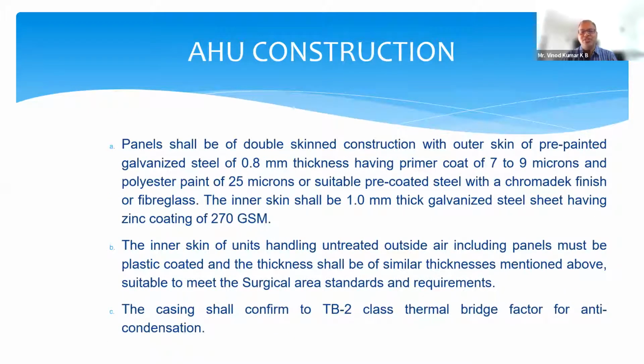Now look at the double-skin AHU construction. The outer skin has to be of 0.8 mm thickness, and the inner skin has to be of 1 mm thickness. That is the construction that we talk about, which is how sturdy the AHU is going to be. These are the guidelines as issued by AHU. So I'm giving you the standards which you can actually copy into your tender specifications, or your consultants whom you have employed can be made to use these standards in their selections. And the inner skin has to have a zinc coating of up to 270 GSM, because this zinc coating is to keep away corrosion inside the AHU.